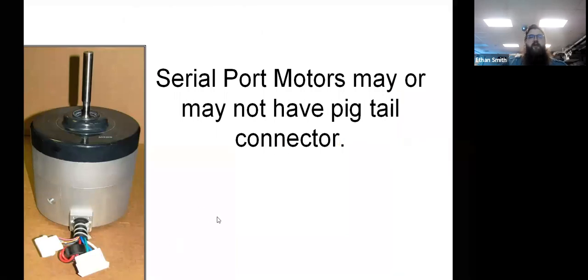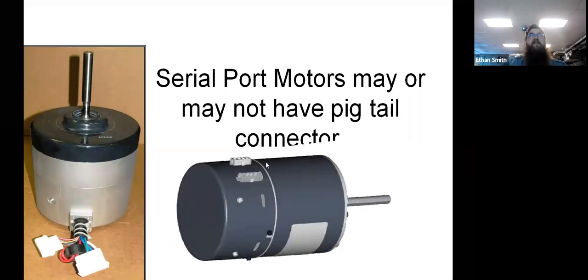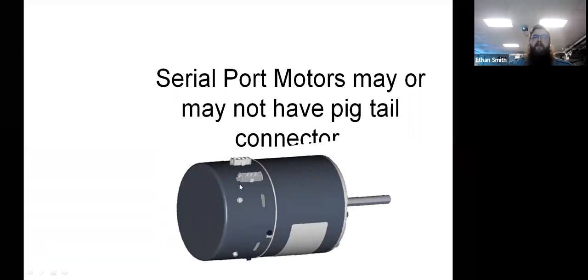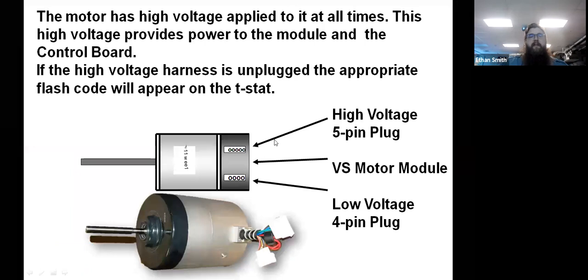Okay, so there's a picture of one. Some of them will have a plug connector like that. Some of them have plugs built into the side of the motor like this. Okay. But it's the same thing. We're sending a low voltage signal and we're always feeding it high voltage. So your first diagnostic check on this is, guys, to check to make sure you've got high voltage from the unit. Okay, that can be 208, 230 in the air handlers or 115 in the furnaces.